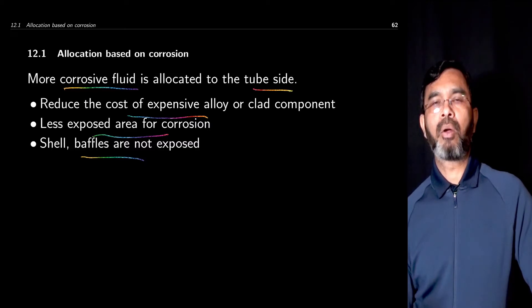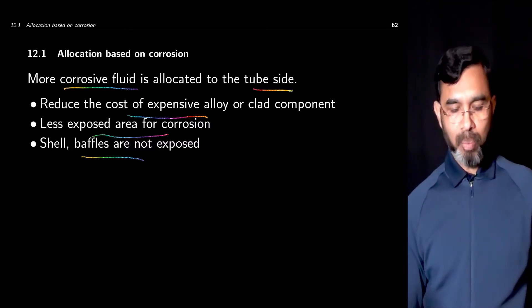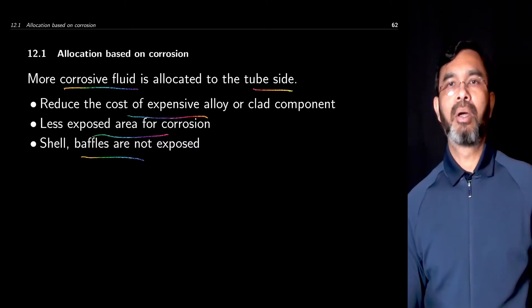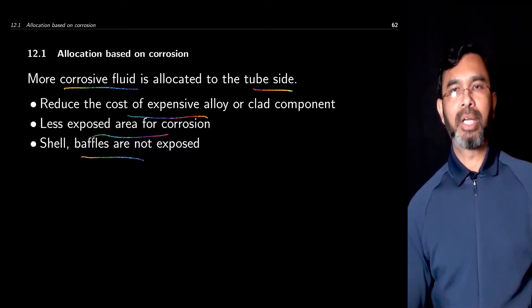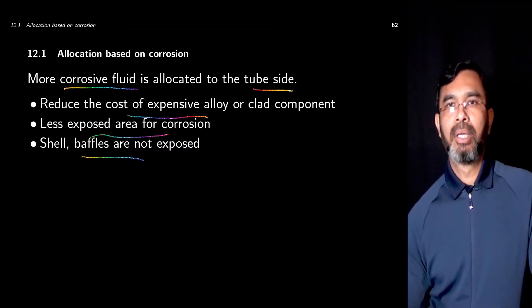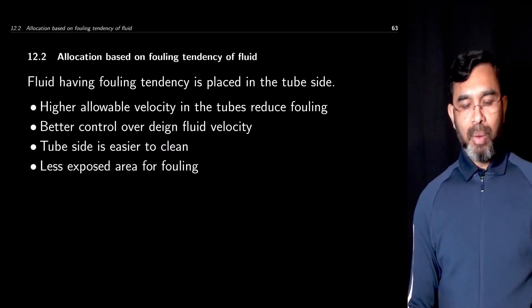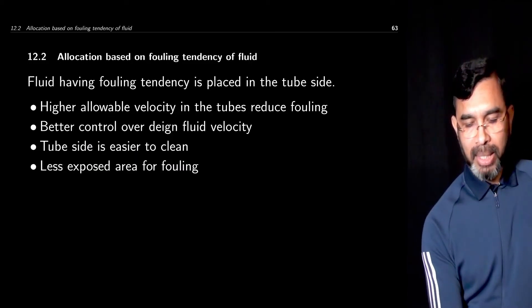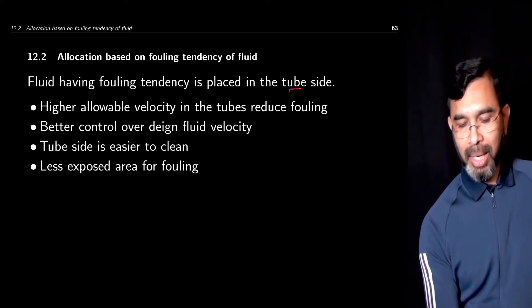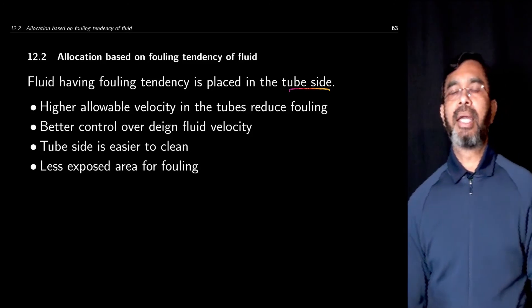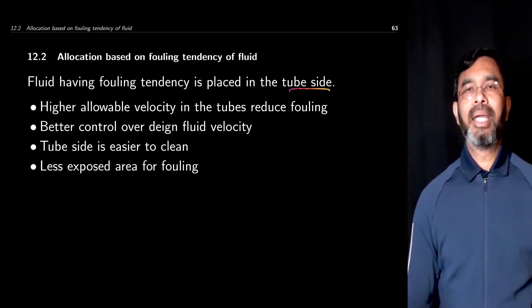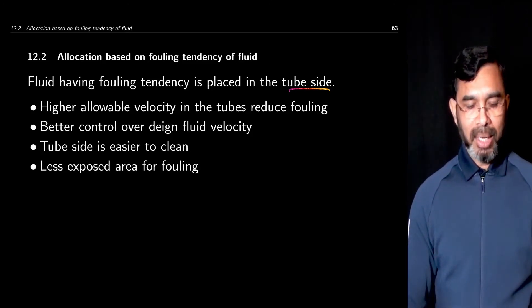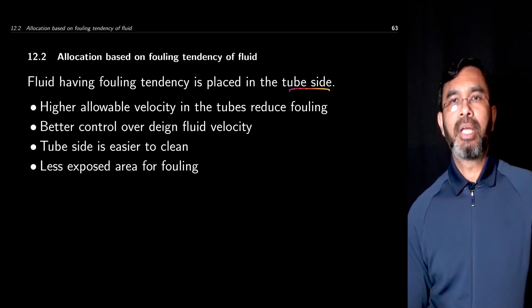If you put the corrosive fluid on the shell side, the outer side of the tubes is also exposed, so the tubes are exposed in either way. Regarding fouling tendency, fluid having a fouling tendency is placed on the tube side. Inside the tube it is easier to clean and there is less area of exposure.